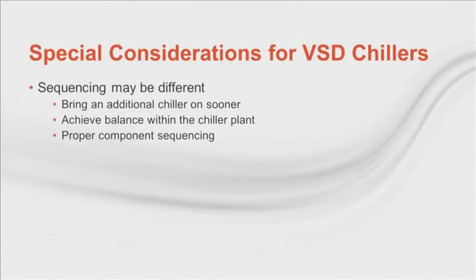We see there is some merit to bringing the additional variable speed chiller on sooner than full load, but not across the board. The savings can be considerable from doing advanced sequencing. I showed earlier the fraction of chillers shipping with drives today, but too much of a good thing is also possible here. A key consideration about variable speed chillers is minimum load.